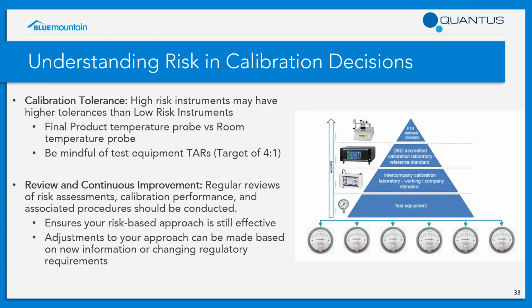Continuing with understanding risks and your calibration tolerances. Your higher risk instruments may have a tighter tolerance compared to your lower risk items. In the example on the screen, you have a final product temperature probe, maybe a much higher risk item, that you would want to assign a tighter tolerance to than the ambient temperature monitoring probe in the manufacturing area that's monitoring your ambient environment. So whatever you choose, you want to be much aware of your target accuracy ratios, or TARs, when you are performing your services.